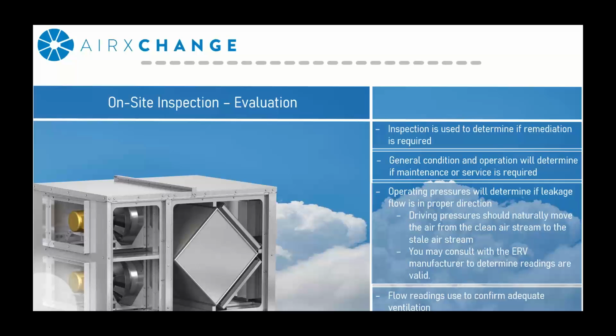Really, all the readings are going to be used to confirm the ventilation rate. And if you find the value is different from what you expected or is required, once again, you may need to consult with the unit manufacturer to determine what steps should be taken to achieve the value that you're looking for.